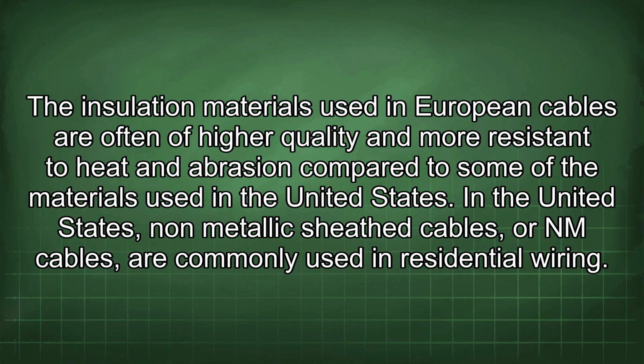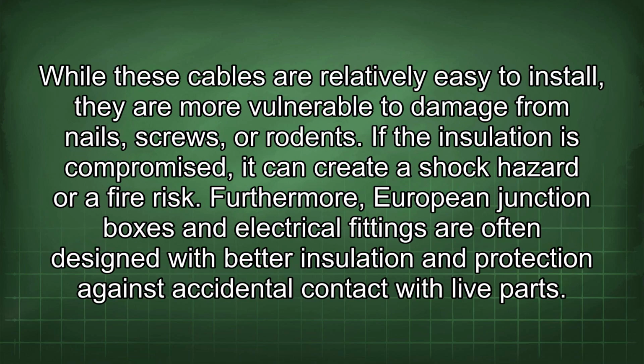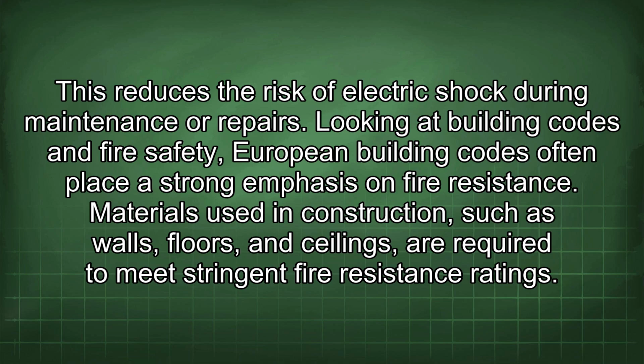In the United States, non-metallic sheathed cables, or NM cables, are commonly used in residential wiring. While these cables are relatively easy to install, they are more vulnerable to damage from nails, screws, or rodents. If the insulation is compromised, it can create a shock hazard or a fire risk. Furthermore, European junction boxes and electrical fittings are often designed with better insulation and protection against accidental contact with live parts. This reduces the risk of electric shock during maintenance or repairs.